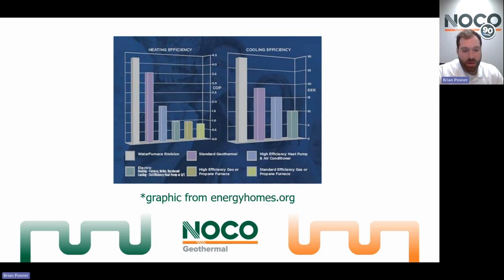Now, once you start using heat pump technology, again, leveraging heat exchange with that electricity rather than drawing the thermal content out of it, now you start getting into the barriers of getting much over a 1 COP. Now you're getting a lot more heat out of 1 unit of electricity than you would have if you just ran it through resistance. So I think on the left side here, we have WaterFurnace, which is our heat pump manufacturer out of Fort Wayne, Indiana. We do use American-made heat pumps that are actually at the top of the line for heat pump technology right now, which is phenomenal. We'll dive a little bit into that a little later.